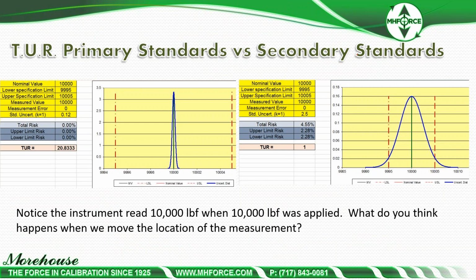Primary versus secondary standard. We're looking at almost the same scenario here. I have a 10,000 pound device. My measured value is 10,000 pounds. Specification limit plus or minus 5. So I have this device. I want to send it to a lab. I send it to the lab with dead weights. I get a TUR of 20.833, and I get a graph that looks like this. I send it, and I'm using that equation. I'm using the CMC, the resolution and repeatability. I have another lab that I think can do the instrument. I send my instrument to them, and at 10,000 pounds, it reads 10,000.